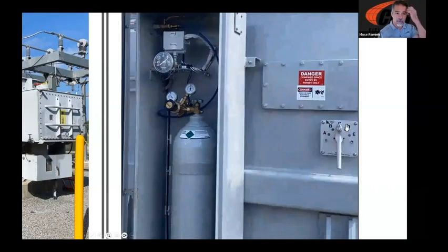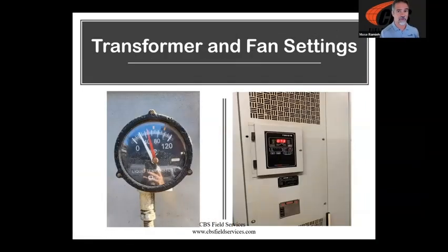Here's another item I want to point out: de-energized tap changers should be locked out. And you guys can see this right here. It's got the A, B, C, D around it. That's not locked. And somebody that's not qualified could easily come up and say, hey, what's this handle do? Move it to a new position and destroy your transformer. So once again, when we're doing our walk arounds, those are some of the little things I'm particularly focused on. Put a lock on there and you automatically improve the reliability of your substation, because now nobody can monkey with your tap changer.